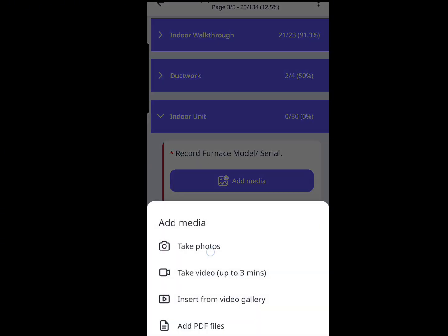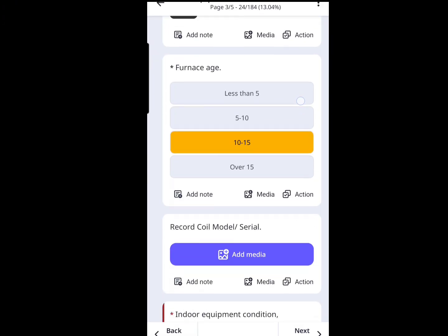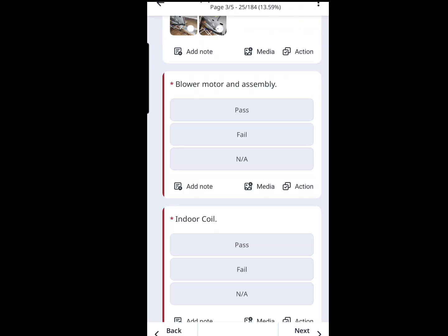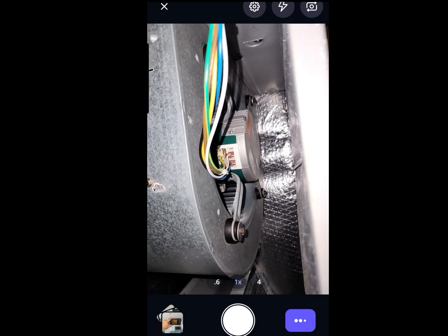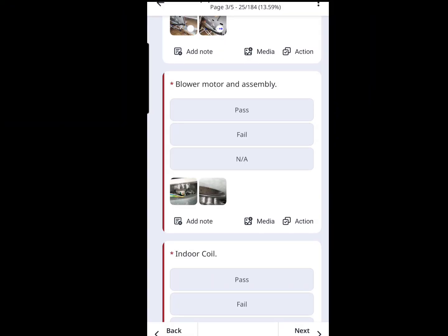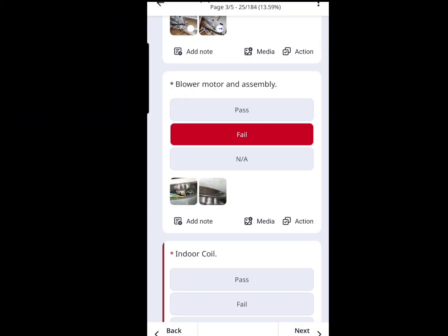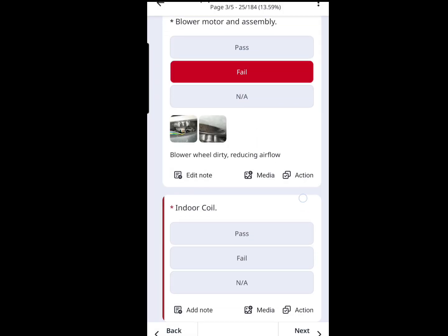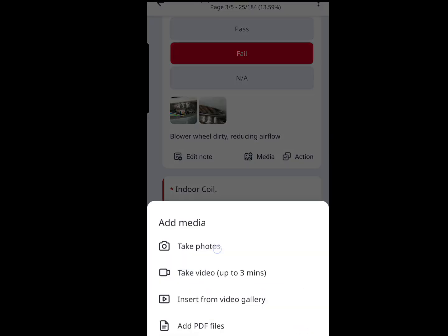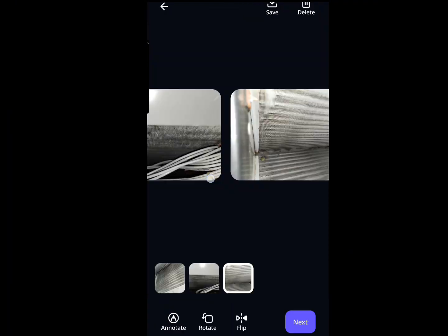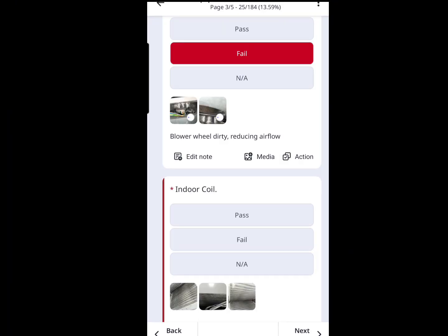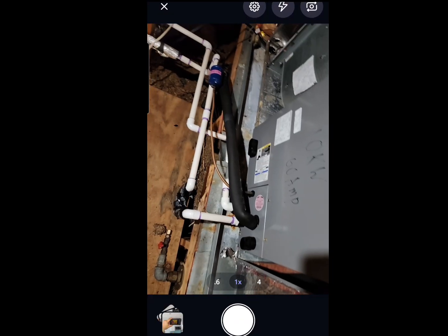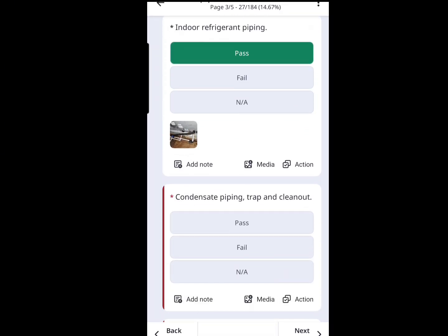Now we get to the indoor unit. We take a picture of the model number, put down the age — 10 to 15 years old — and the general condition. Everything gets photo documented. We zoom into the blower motor and blower assembly — it's a little bit dirty, so that gets a fail and gets flagged in the report. Next, we take a look at the indoor coil and grab some photos — that doesn't look too bad. Then we document the condition of the refrigerant piping, making sure there are no signs of leaks and that the insulation is intact and installed properly.